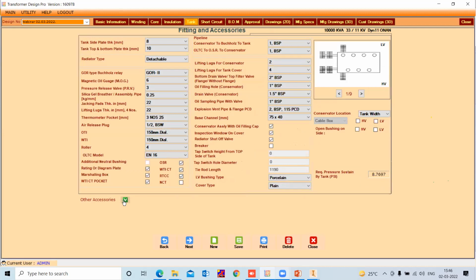Now let's see the other accessories. So for this 10 MVA, you can see all the required accessories are available, like OLTC model, OTI, WTI, and which kind of OTI and WTI is required is all automatically decided by the software. But still, if you want to choose anything from the drop down as per your customer requirement, then you can select from here. Then it will impact the bill of material as well as the manufacturing drawing. You can see the cable box option as well as the bare bushing option on the side. So all the options are available. Using these options, you can manipulate or generate your diagrams in 3D as well as in 2D.